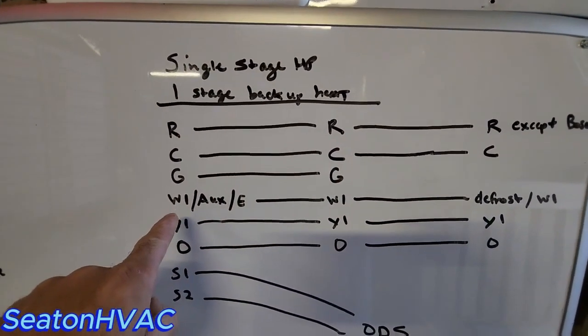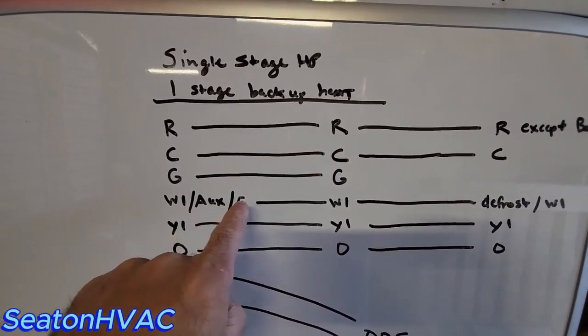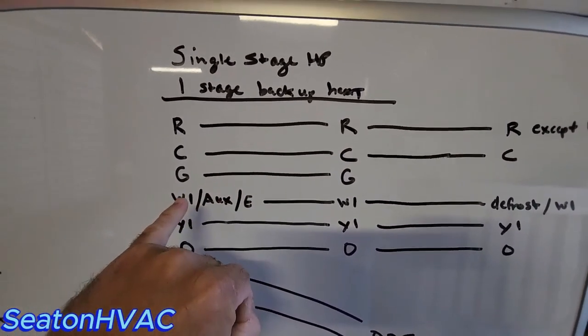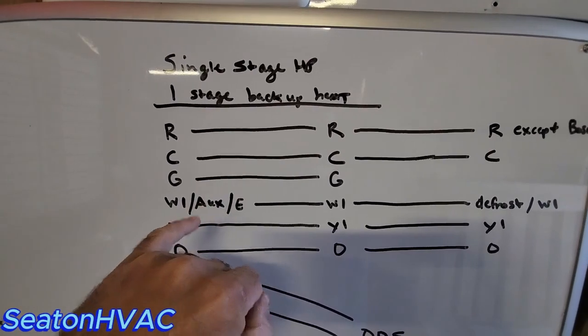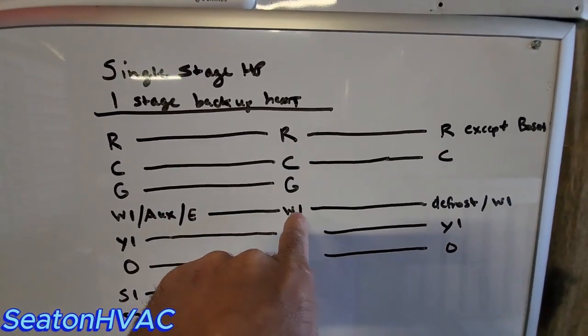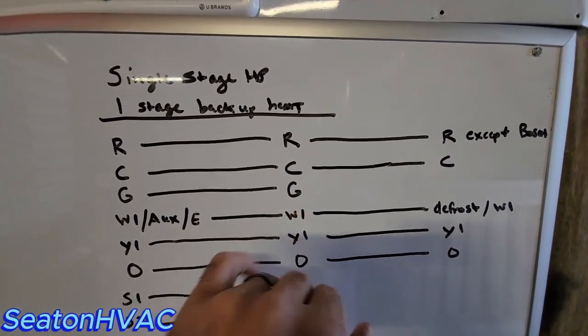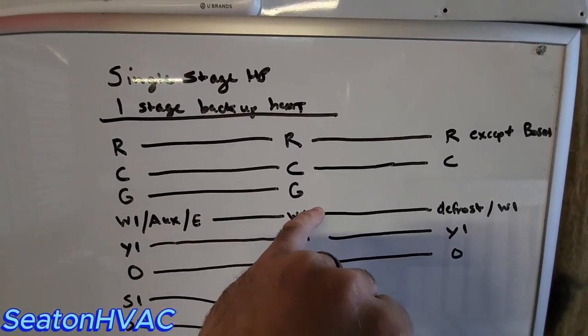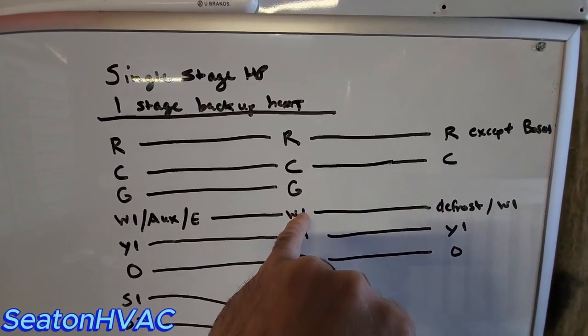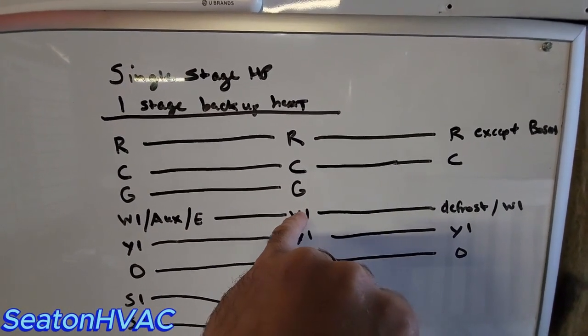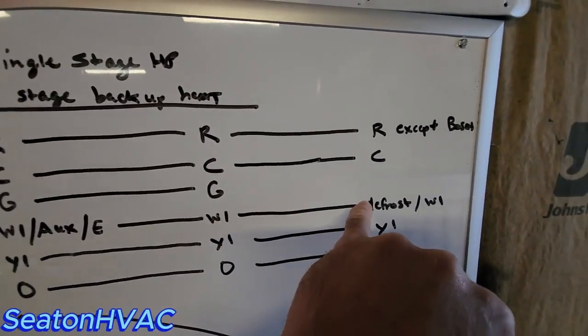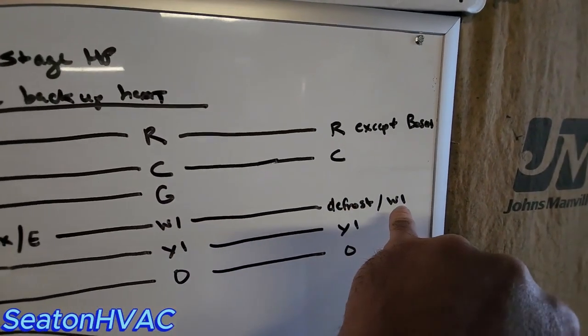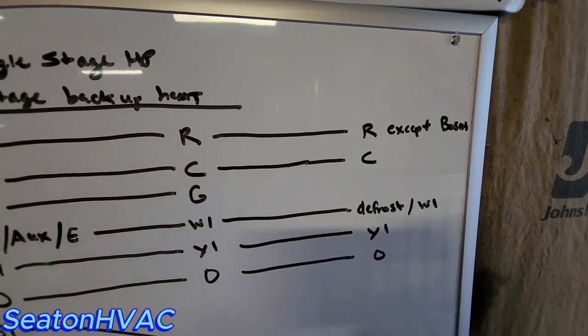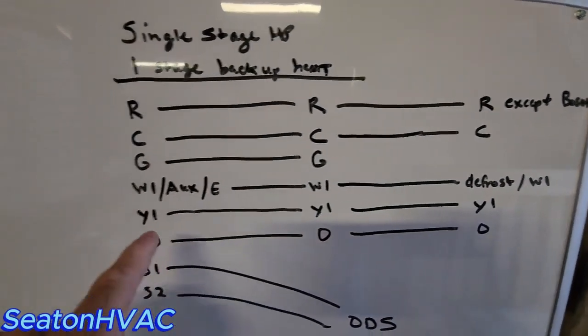Then you have, I'm going to call it on a heat pump, W1, auxiliary E. They're usually all the same terminal. You'll just have to change the programming. That's your white wire that goes into your air handler. Wire nut it. Sometimes there's two wires there that need to energize all of your banks of heat strips. So sometimes you'll have to wire nut 3 wires together there. And then your white wire continues outside. I'm going to call it defrost W1 for outside because it's going to come on during defrost, okay?